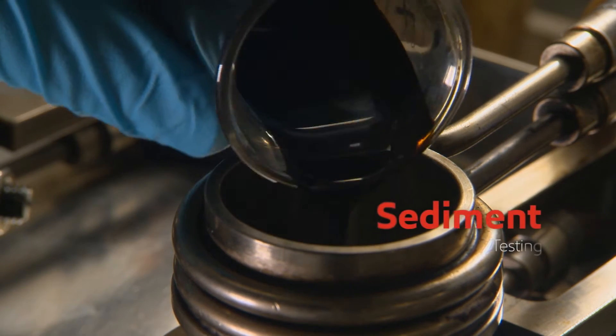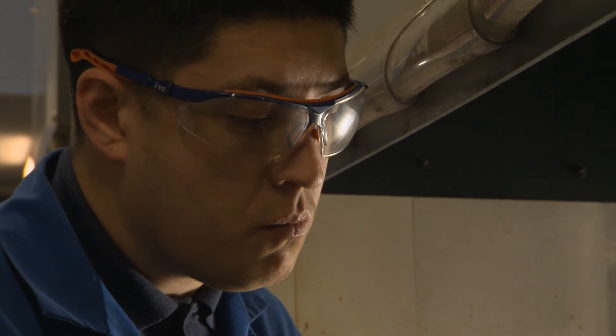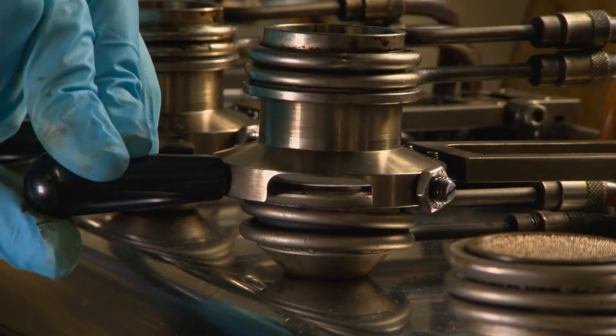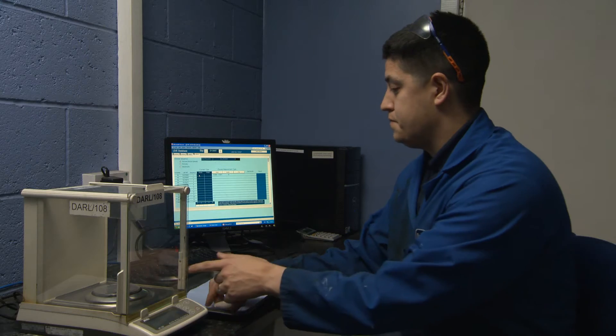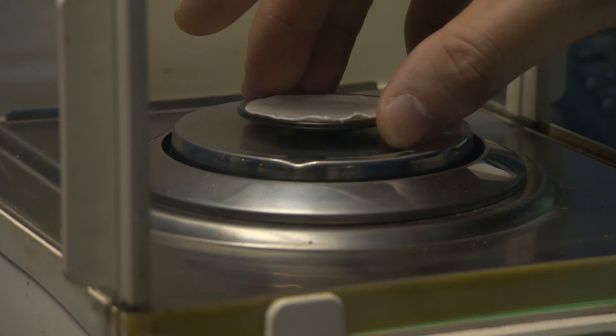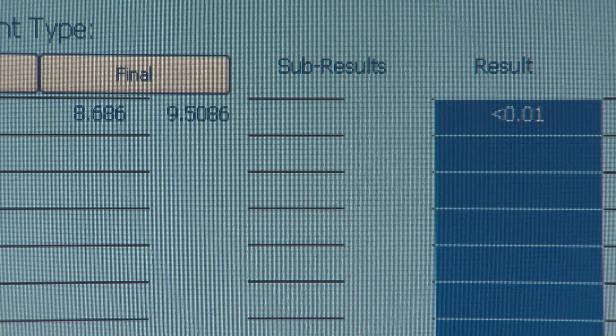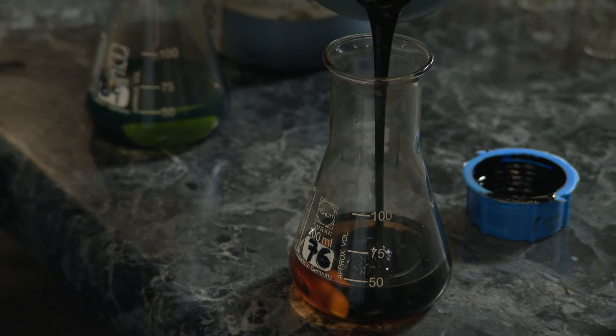Sediment testing is generally carried out in fuel testing labs. The sediment test within ISO 10307 is the total sediment potential test, which looks at the material contained within the fuel. The fuel is maintained at an elevated temperature overnight for 24 hours and is then vacuum filtered to look at the residual weight of the sediment actually present within the fuel.